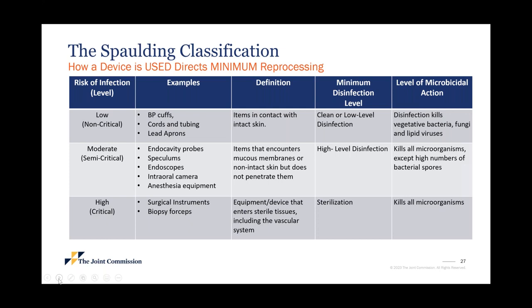However, if it's going to be used on a mucous membrane - and here's the big one I always think of, endocavity probes, speculums, things you may have done in an office - the minimum level of reprocessing is high-level disinfection. Can you choose to sterilize your speculums? Absolutely. But our requirement and the FDA's requirement is that the minimum level of reprocessing is high-level disinfection.